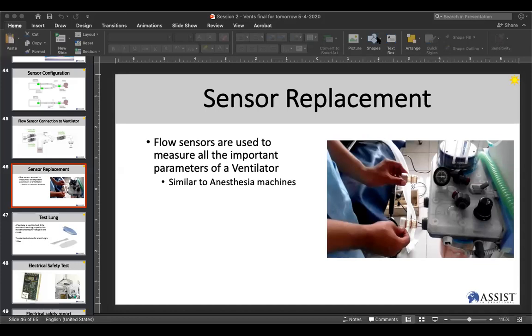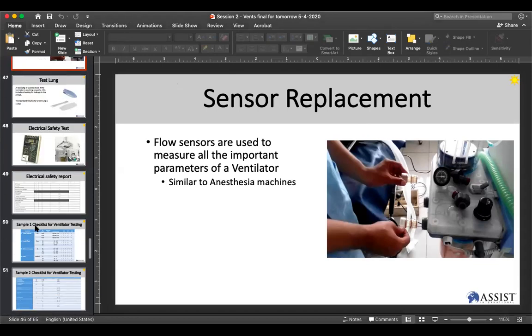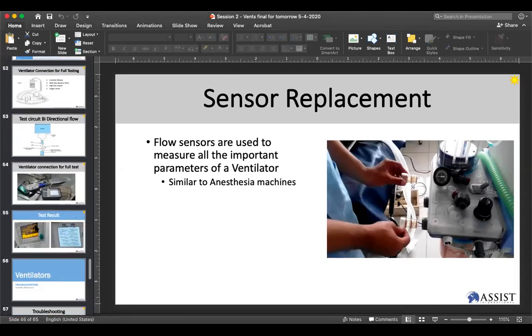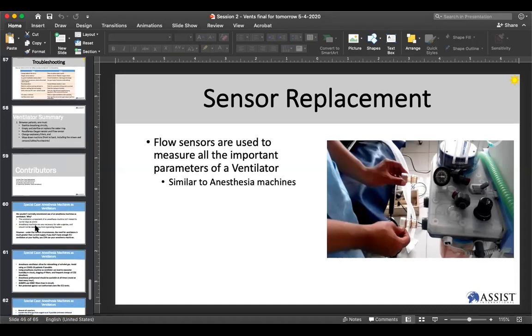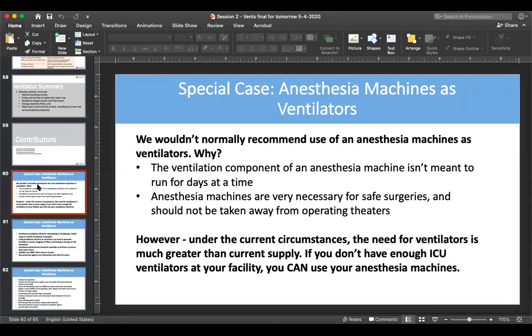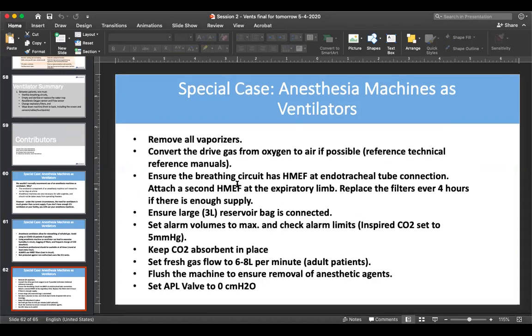So we have some questions from the chat. Let me go ahead and read some of these off. When it comes to using anesthesia as a ventilator, the vaporizer is in place, but what about soda lime and replacing the soda lime? I should mention, I believe you need to remove the vaporizer. Is that true, Benjamin? Correct, absolutely. So we want to remove all of the vaporizers from the circuit.